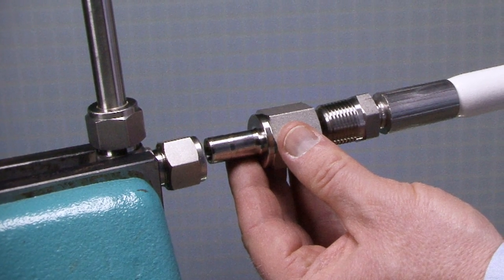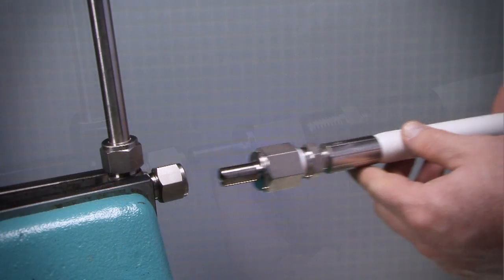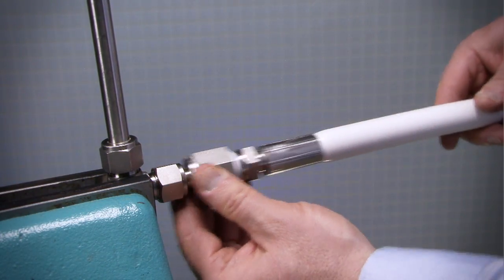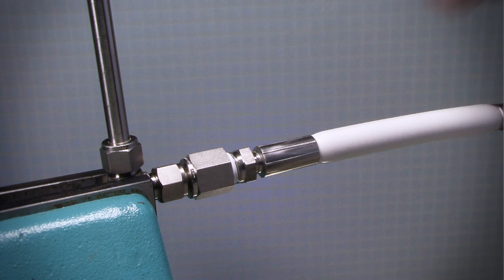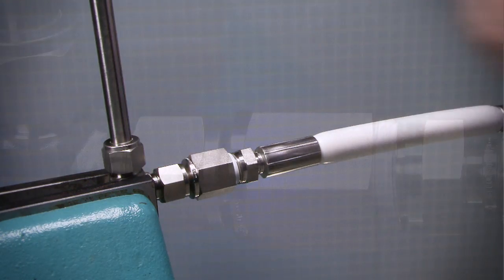Install the end connection opposite the tube adapter first. Insert the tube adapter into the Swagelok tube fitting. Make sure that the tube adapter rests firmly on the shoulder of the tube fitting body and that the nut is finger tight.